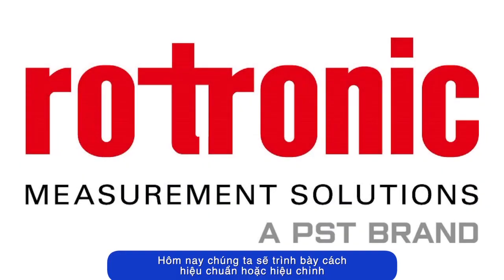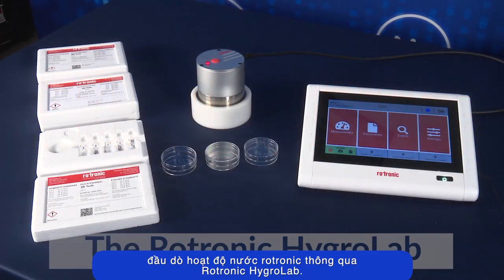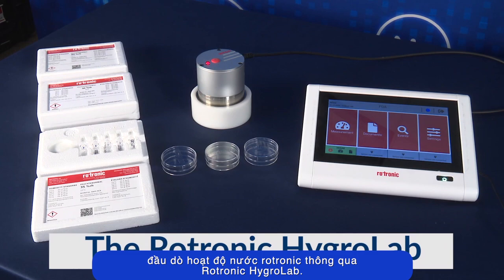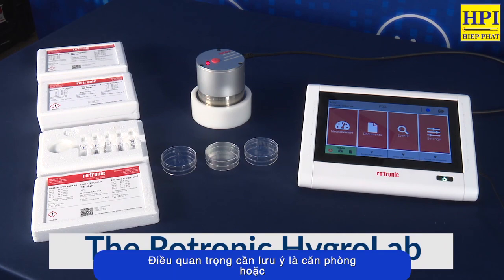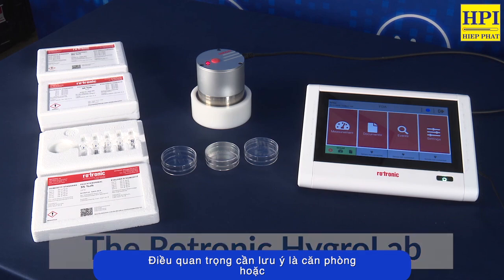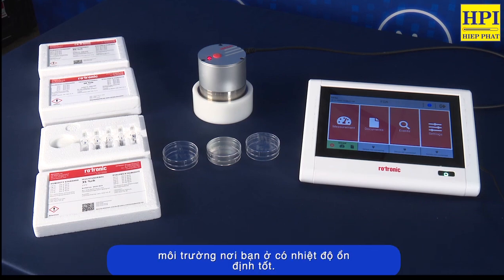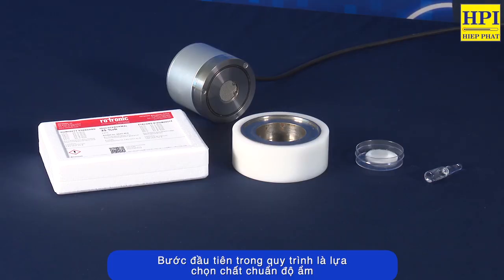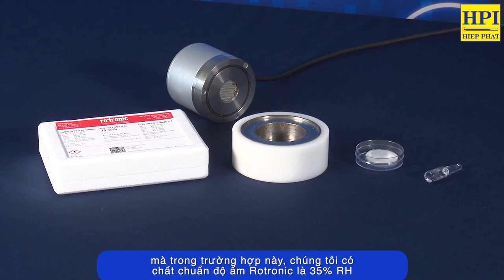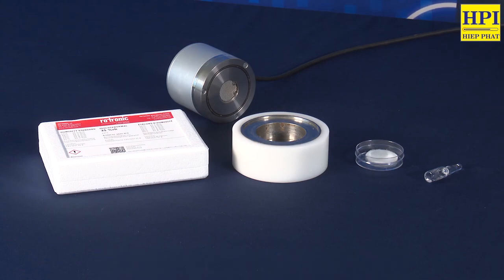Today we're going to demonstrate how to adjust or calibrate your Rotronic water activity probe via the benchtop unit HygroLab. It's important to note you want the room or the environment you're in to be of good temperature stability. The first step in the procedure is to select a humidity standard. In this case, we have 35% RH, certified Rotronic humidity standard.